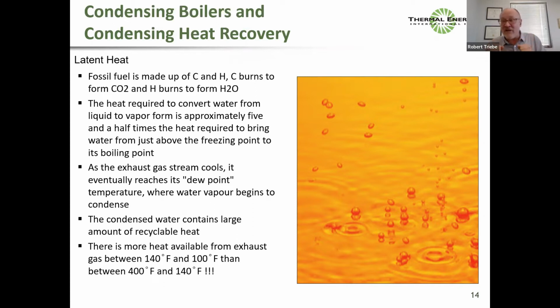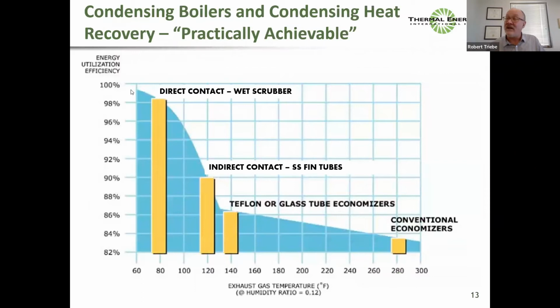There's more heat available between 140 and 100 F. So over 40 degrees, there's more heat available than in the previous 350 degrees. So if I cool your flue gas from 400 to 140, I get less energy than if I cool it from 140 to 100. And so that's why these low temperature sinks and integration become so critical. That integration determines what part of this curve your system's going to perform on.